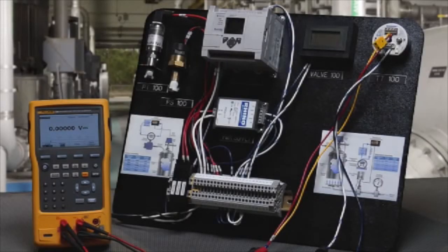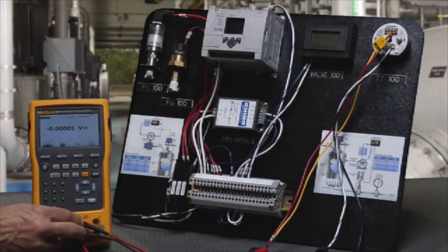In this example, we're going to test an RTD input temperature transmitter using the Fluke 754 documenting process calibrator. We're going to power the transmitter and measure the milliamp signal measured back on the milliamp input jacks of the calibrator.